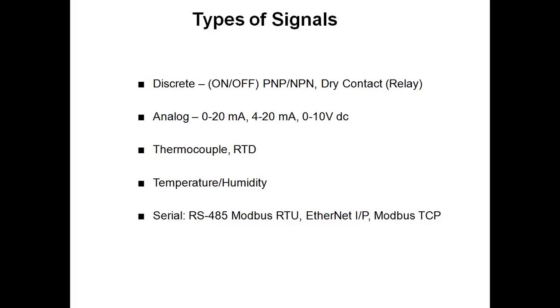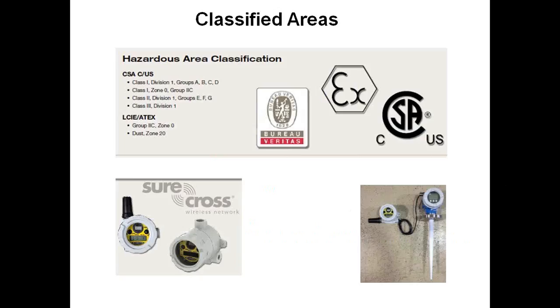As far as signal types, we can handle just about anything - discrete I/O, which would be on-off, PNP, dry contact, relays, various analog signals from 0 to 20, 4 to 20, or 0 to 10 volts, thermocouple, RTD. We also have some special serial probes that do temperature and humidity. And we can handle typical RS-485, Modbus, Ethernet, and Modbus TCP signals.